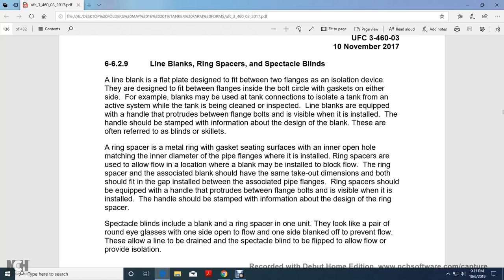Inspect the line blanks. Each is equipped with a handle that protrudes between the flange bolts and is visible when installed. The handle should be stamped with the information on the design of the blank. They are often referred to as blinds or skillets.